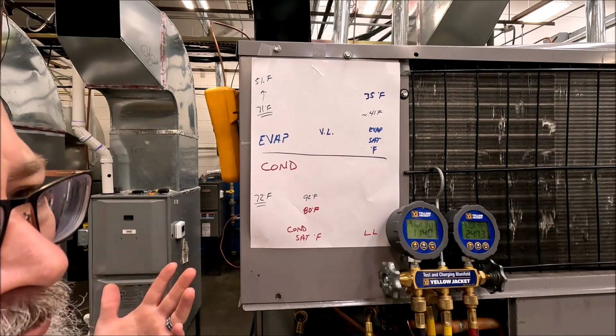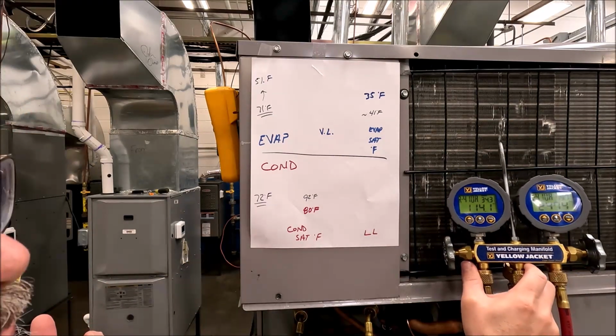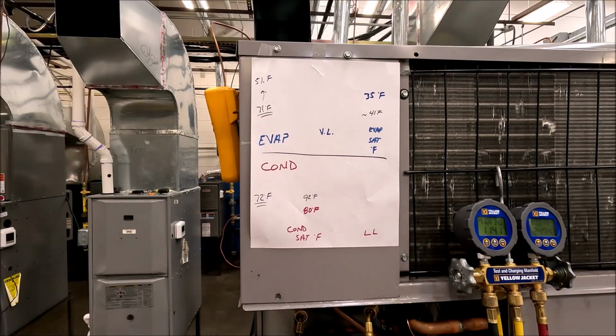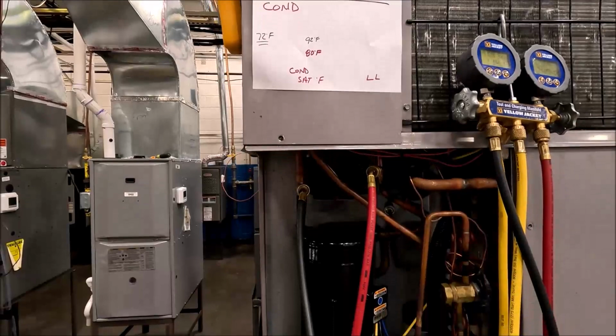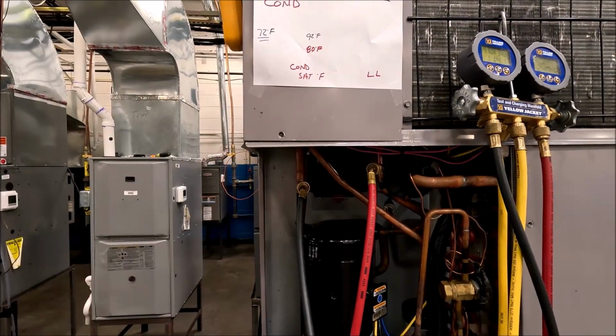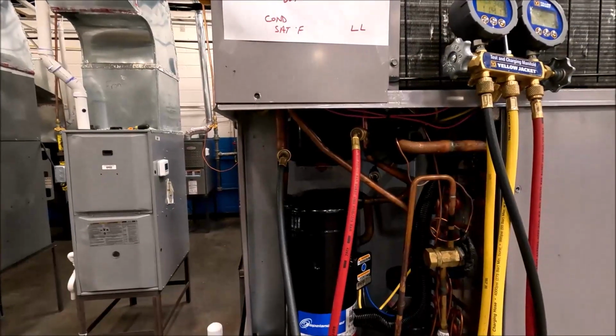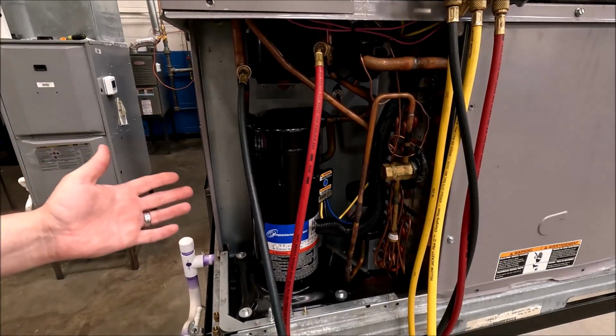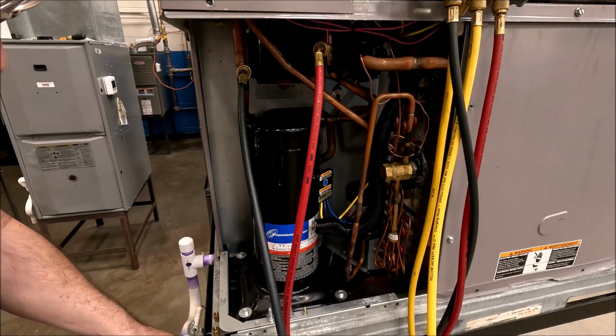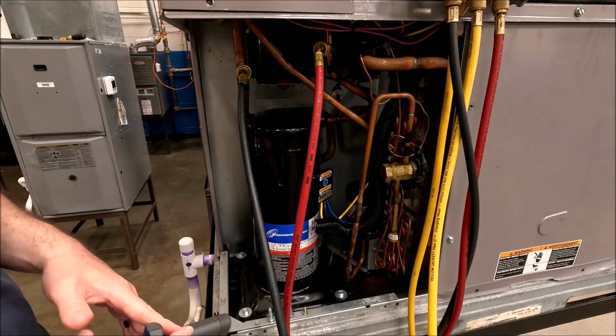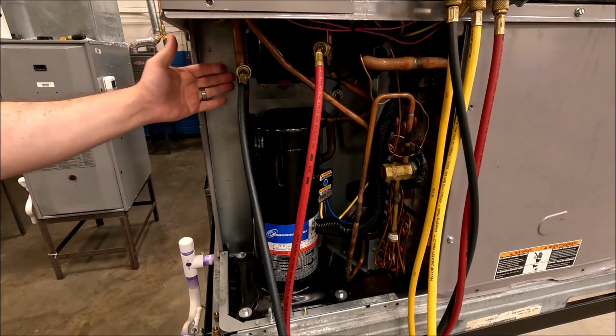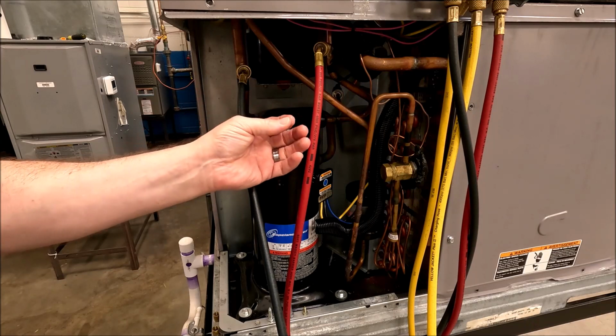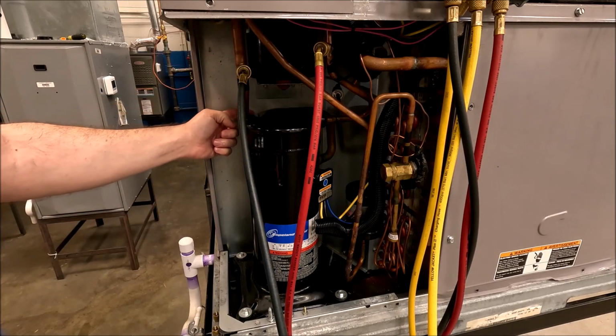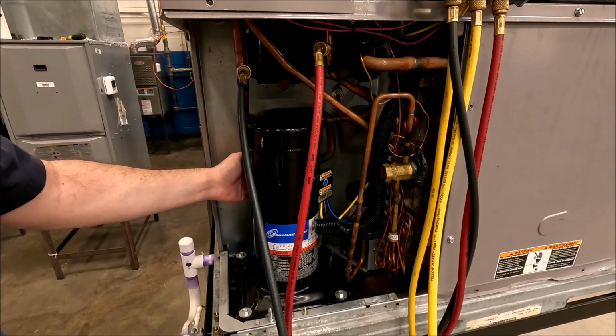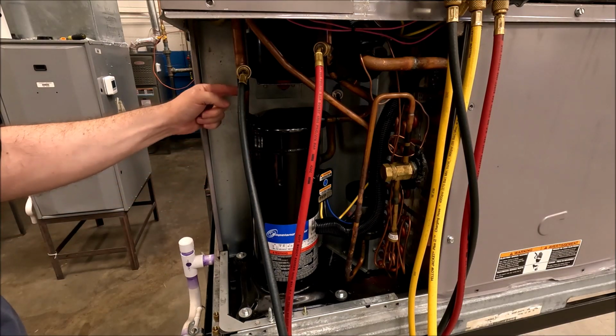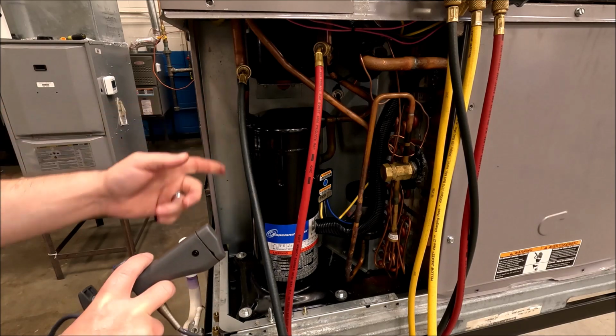But what do you do with that number? You can't do anything with that number yet. You need to actually check your superheat and subcool. So where do you check that? If we come back down to the compressor area, what we need to look at is the superheat and subcooling points. I've got a pipe clamp right here that I'm gonna use. This line that we looked at earlier, I refer to it as the vapor line. This thing is cold and wet, and it's got a little bit of oil on it too. But it is going into the compressor. That's the vapor line from the evaporator side. So I know that is where I need to check superheat.